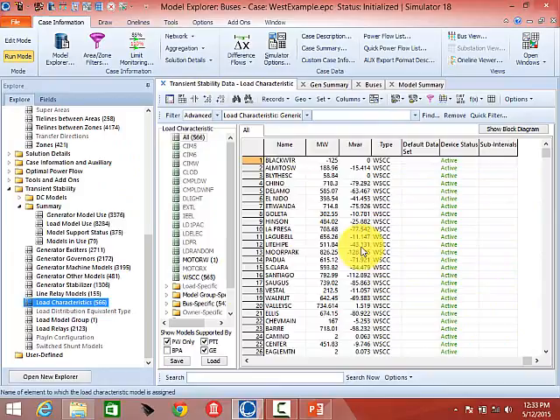Loads are a little tricky because with generators there's a specific generator with specific parameters, so generator models are all unique. What's often done with load models is you can define load model parameters at a hierarchy of different locations — you can define one single load model for the entire case, for a particular area, for a particular bus, or for a particular load — and there are a couple of different ways to do it.